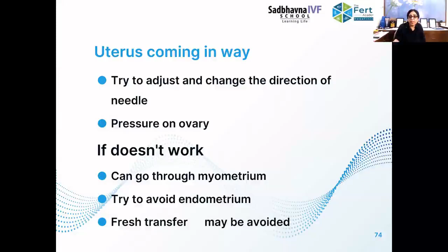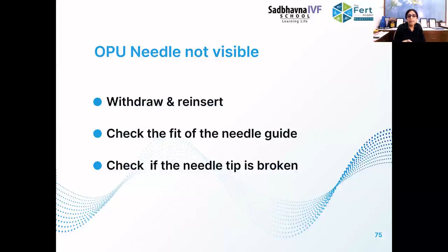Yes, the needle guide gets dislodged a little bit and then you cannot see the needle. So you must check the fit of the needle guide, and there should be a click if you're using those disposable ones, because they become loose after some time. And then when you withdraw the needle, see if the needle tip is broken, because the tip is the echogenic part which you see.